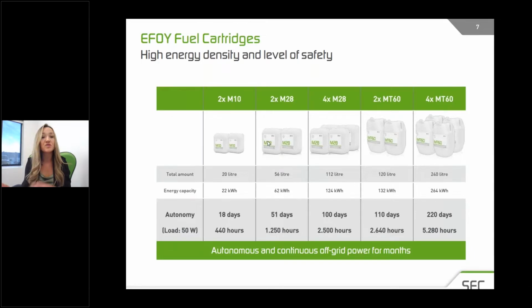Keep in mind, the fuel cell is only going to start and stop based on battery voltage. So when we're sizing these systems, I'll ask: what is your desired autonomy to achieve at site? How frequently do you want to go out and replace the fuel cartridges? A lot of our oil and gas clients only want to visit site once a year, typically after the winter, so we'll size a system for replacing the fuel once a year.